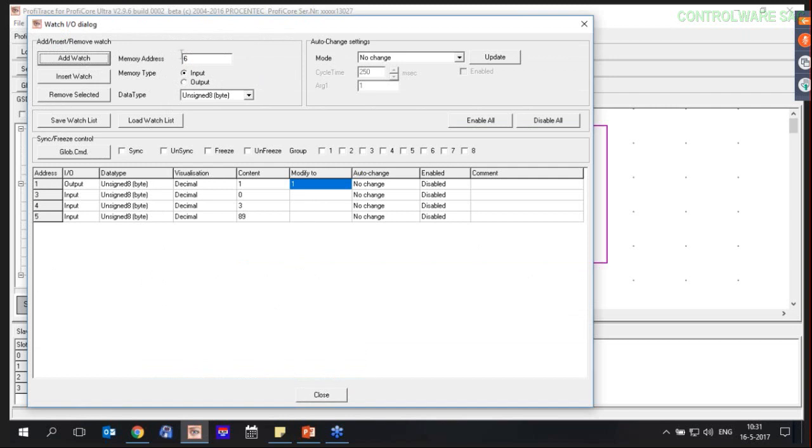I think the 3 up till 6 is a floating point value. I don't know, but let's try. Nope. But over here I can see a value. Let's see if I can change something. Yeah, you see the value is changing by changing the analog input. So now I can see if my device is sending over the correct data.